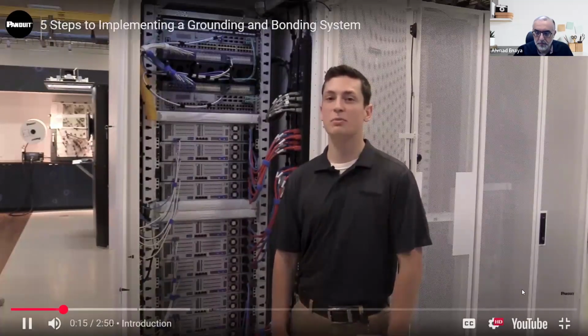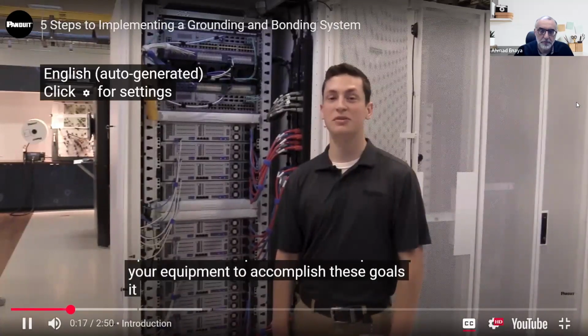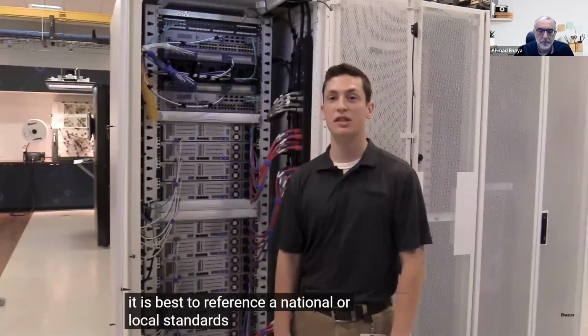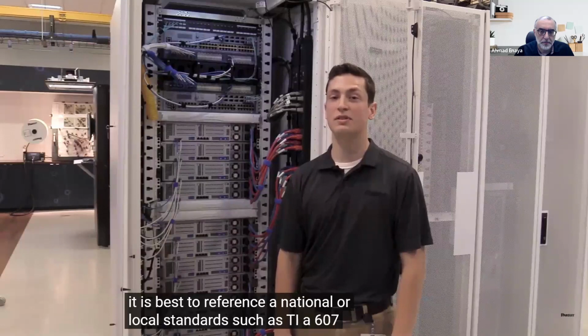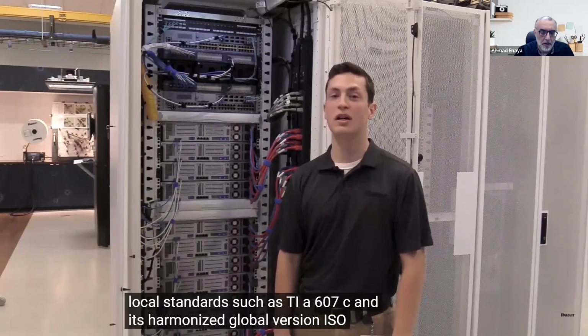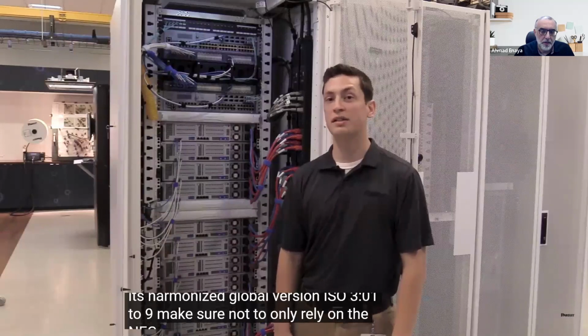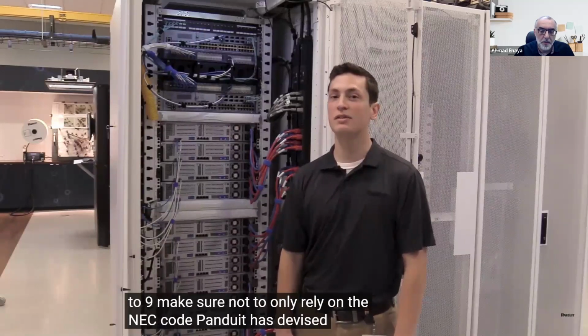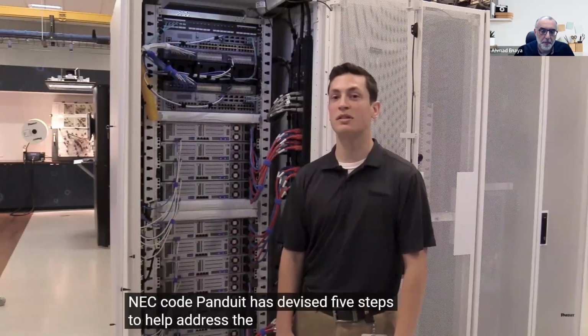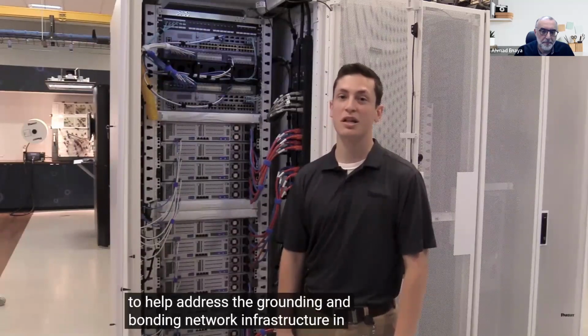Hi, my name is Brendan Haas, I'm the product manager of grounding and bonding solutions at Panduit. Grounding and bonding can do more than just protect personnel from electric shock—when done properly and intentionally, it can also optimize network performance and protect your equipment. To accomplish these goals, it is best to reference a national or local standard such as TIA 607C and its harmonized global version ISO 30129. Make sure not to rely only on the NEC code. Panduit has devised 5 steps to help address grounding and bonding of network infrastructure to make sure you have the correct products you need.